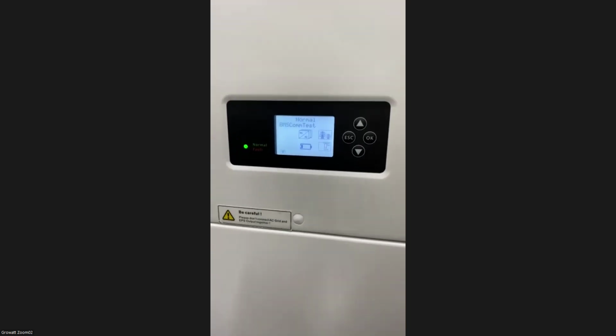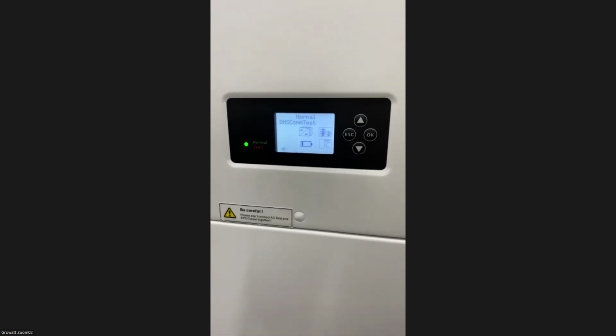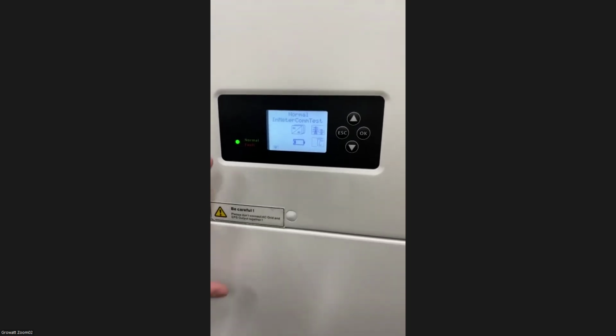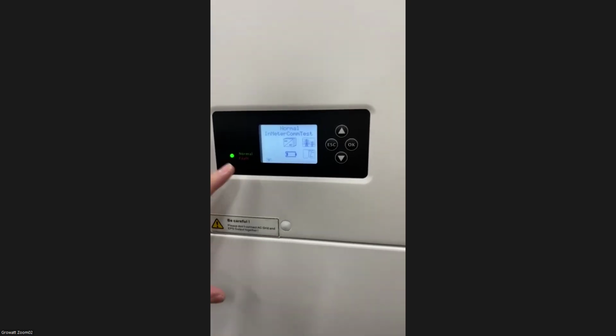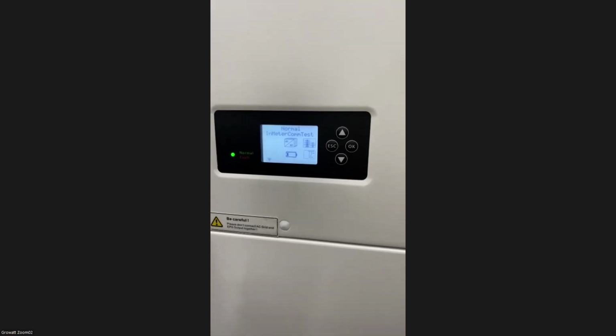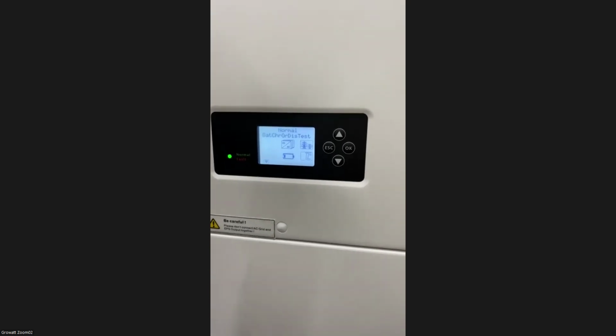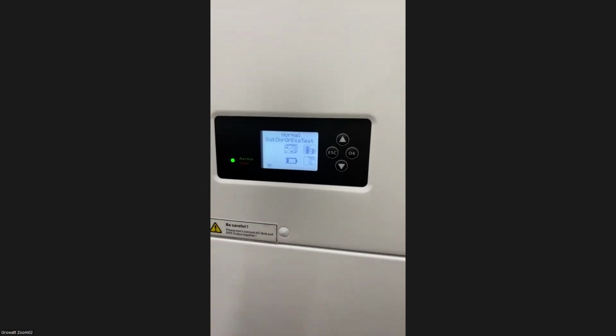Right now it's going to start with the BMS communication test, testing whether the battery is communicating, then it's going to test the meter, and now it's moving on to the battery charge and discharge test.